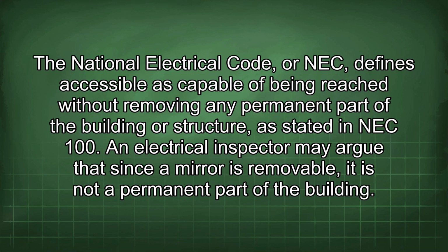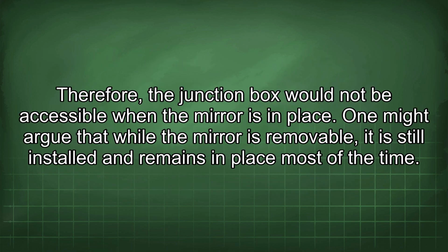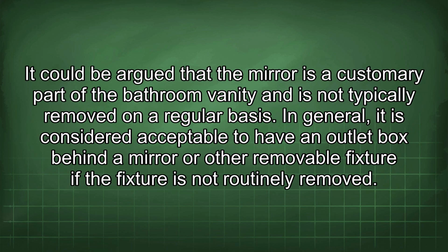An electrical inspector may argue that since a mirror is removable, it is not a permanent part of the building, so the junction box would not be accessible when the mirror is in place. One might counter that while the mirror is removable, it is still installed and remains in place most of the time, and is a customary part of the bathroom vanity not typically removed on a regular basis.